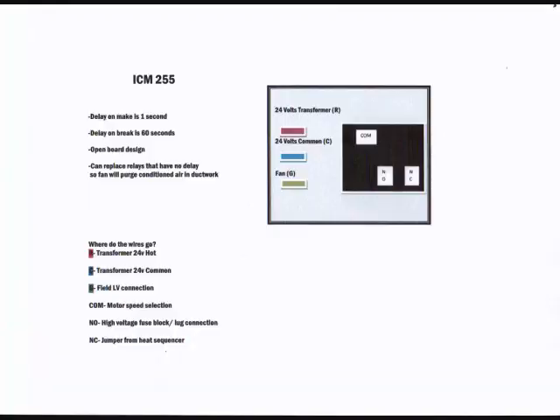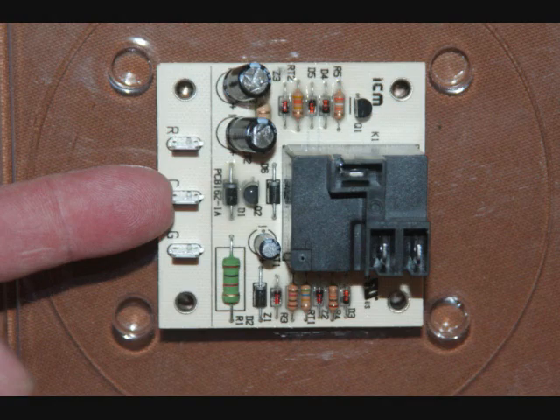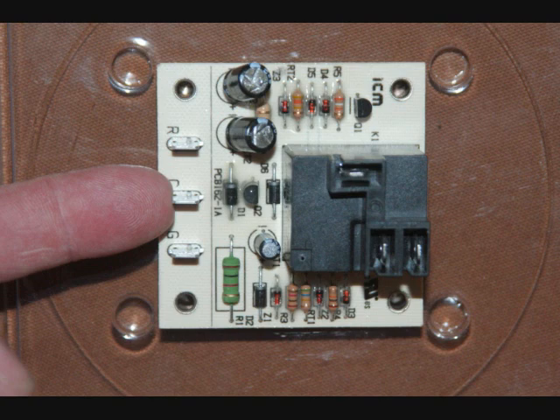Next one down you'll see the 24 volts common. That'll run back to the other side of the transformer. Typically blue, brown, or black color. It'll just be on the opposite side of the transformer as your red. And that is the location on the actual board where you would wire it up.